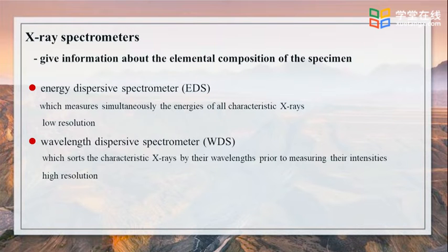The wavelength dispersive spectrometer, called WDS, makes use of Bragg reflection from a crystal and operates in serial mode, the spectrometer being tuned to only one wavelength at a time. Several crystals of different interplanar spacings are needed in order to cover the required wavelength range. The spectral resolution of WDS is better than that of EDS, but the latter is faster and more convenient to use.